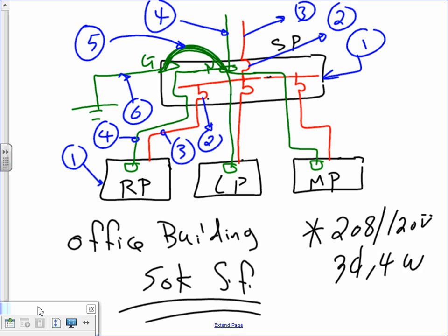One more time. We have a service, number three, service entrance conductor coming to a service panel. Then feeders going to three panels. We have the neutral going from the utility into the service panel, into all the other panels, and we have a grounding electrode conductor going to the ground bar, or the ground rod, or the steel of the building, and we have a bonding jumper, typically a screw, a little green screw. So we need to size that one.